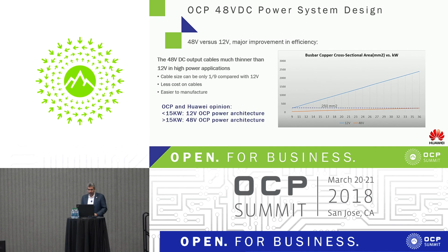cross-sectional area. We're looking at this graph from 9 kilowatts to 36 kilowatts. The orange line is the 48 volt, blue line is the 12 volt. One thing I want to point out is that the biggest bus bar you'd use at 36 kilowatts in 48 volt is actually the smallest one we're starting with at 9 kilowatts for 12 volt—that's the 250 millimeter squared line.